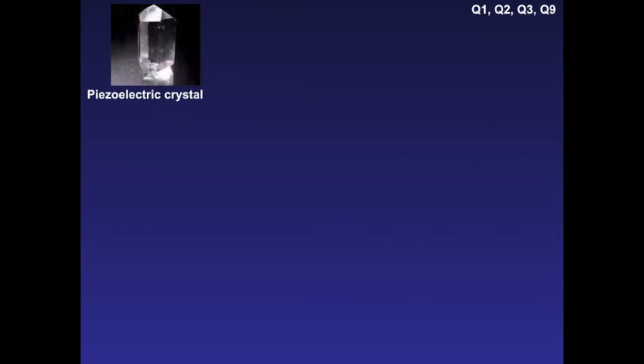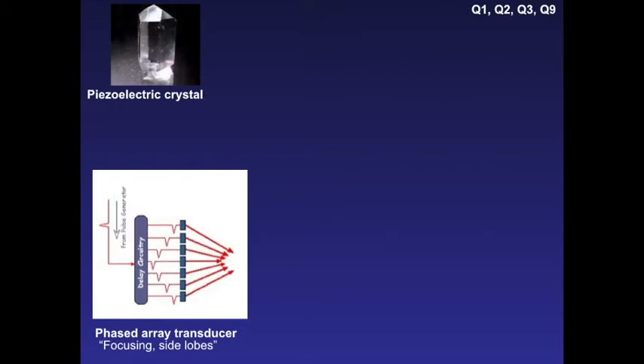So it starts traditionally with a crystal, quartz, or ceramic called a piezoelectric crystal, pressure piezo to electricity. What happens is if you apply a current to it, it emits a frequency of ultrasound. We'll liken it to a bell, where the electrical current is ringing the bell, striking the bell, and creating a sound. This electric crystal can be arranged in an array, as in this diagram here, where you can phase this array in a transducer, and by phasing it, you can focus the beam and obtain better images.